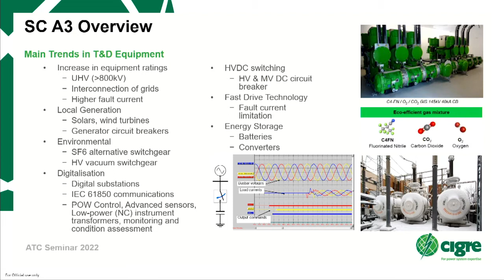The environmental trends include SF6 alternative switchgears and high voltage vacuum equipment. Digitalization, including IEC 61850 communications, point-on-wave control, advanced sensors, low power non-conventional instrument transformers, monitoring and condition assessment. High voltage DC switching, including high voltage and medium voltage DC circuit breakers. Fast Drive Technology, including fault current limitations. Also energy storage, including batteries and converters.